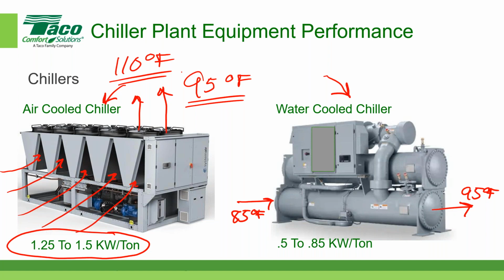And the amount of energy that a water-cooled chiller consumes is significantly less. It's somewhere in the range of 0.5 to 0.85 kW per ton. Obviously, some manufacturers are going to have a little bit less energy consumption, and others will be a little bit more. We're just looking at orders of magnitude here, just to get us oriented. So, since a water-cooled chiller uses significantly less energy, we're going to focus our attention on water-cooled chiller plants today. Any questions out there, Brett, before I go into a little bit more detail about water-cooled chillers?